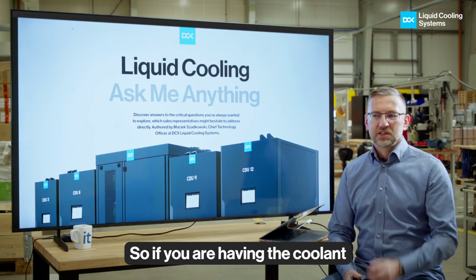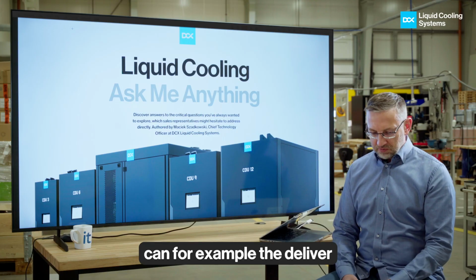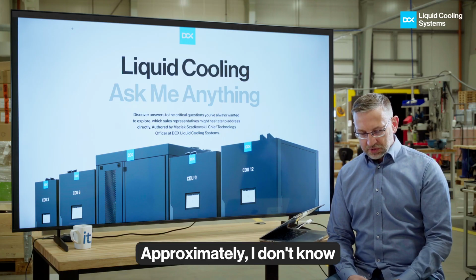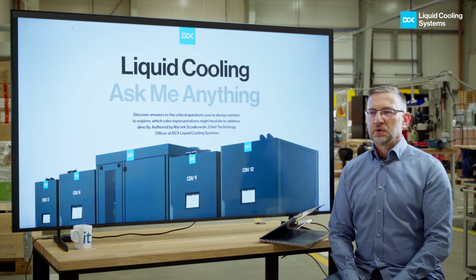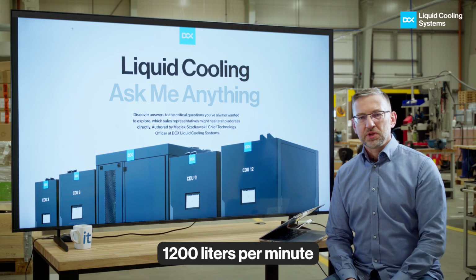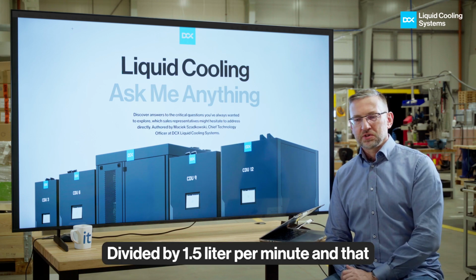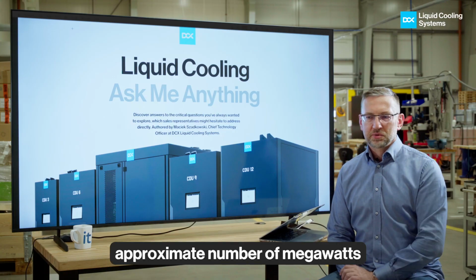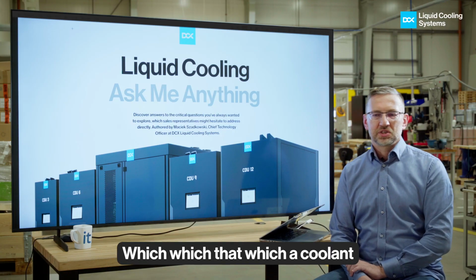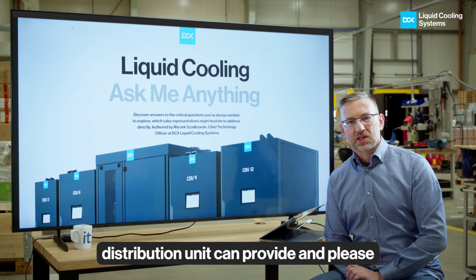So if you have coolant distribution units which can, for example, deliver approximately, I don't know, 1,200 liters per minute, divide by 1.5 liters per minute, and that will give you the approximate number of megawatts which that coolant distribution unit can provide.